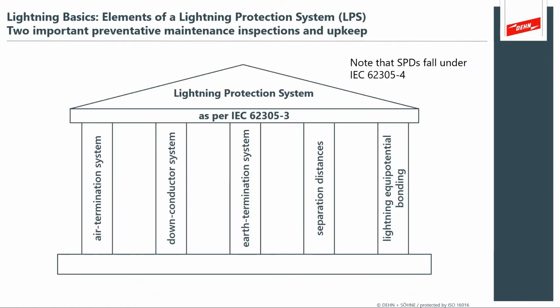So the lightning basics: the air termination system, this is the Ben Franklin rod. The downcomer system brings that lightning stroke to the earth termination system. All the while you're paying attention to separation distance between the metal bodies of the lightning conduction system and your electrical apparatus. And where you cannot separate, you use lightning equipotential bonding to reduce side flash. This constitutes what is considered a lightning protection system.